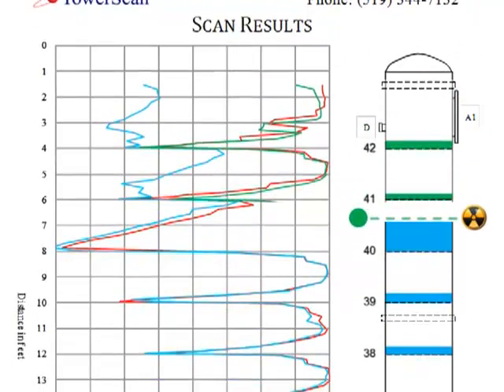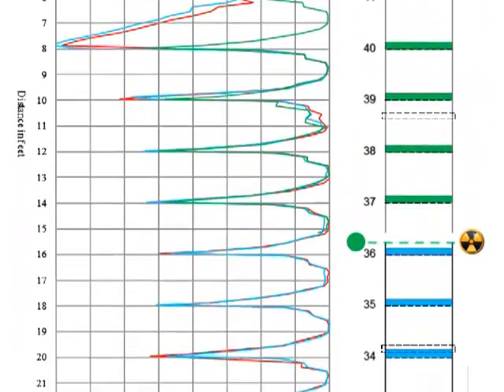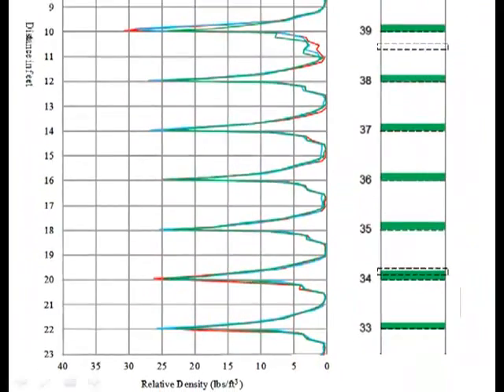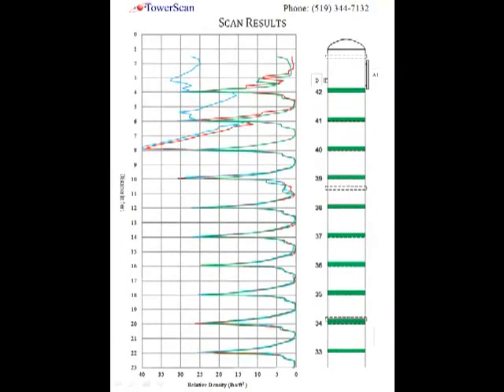A post-wash follow-up scan was performed and showed that the trays were now all consistently loaded and operating with good liquid-vapor disengagement.